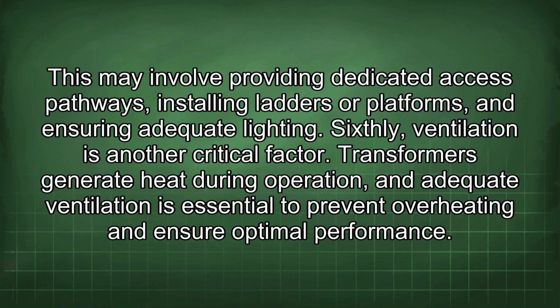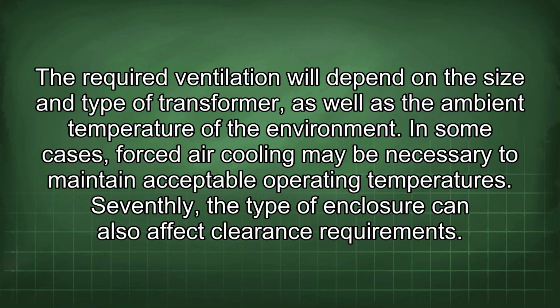Sixthly, ventilation is another critical factor. Transformers generate heat during operation, and adequate ventilation is essential to prevent overheating and ensure optimal performance. The required ventilation will depend on the size and type of transformer, as well as the ambient temperature of the environment. In some cases, forced air cooling may be necessary to maintain acceptable operating temperatures.